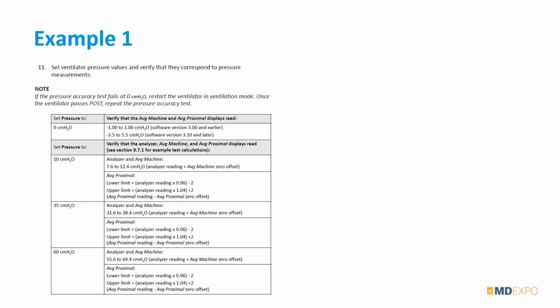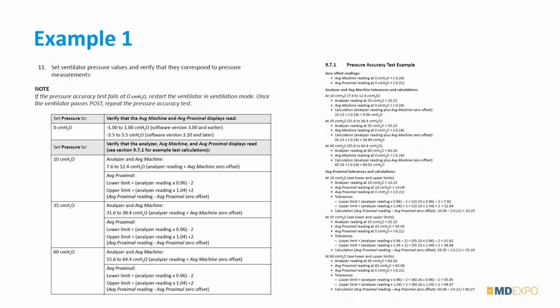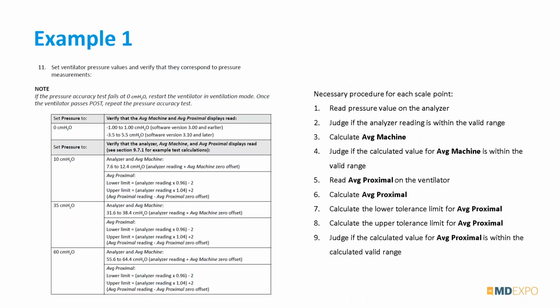But sometimes you see things like this where it's very complicated. So here they ask you to apply pressure and then calculate your upper and lower acceptance limit yourself based on the measurement on your gas flow analyzer and on the ventilator. So there's a whole procedure, and they figured out that this is quite complicated, so they even added calculation examples in the appendix, so what you have to do. So we simplified it for you a little bit. In total, in this case, they ask you to go through 9 steps of taking a look at measurements, then calculate some valid ranges, and then interpret if your measurement is actually inside that calculated valid range.